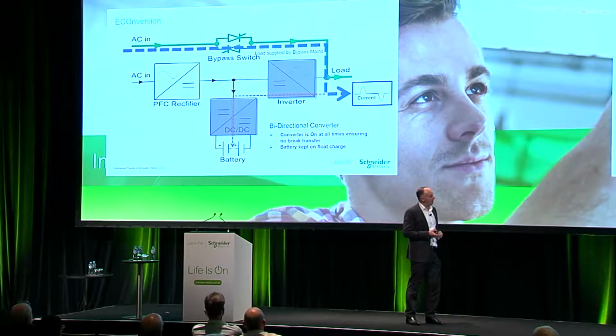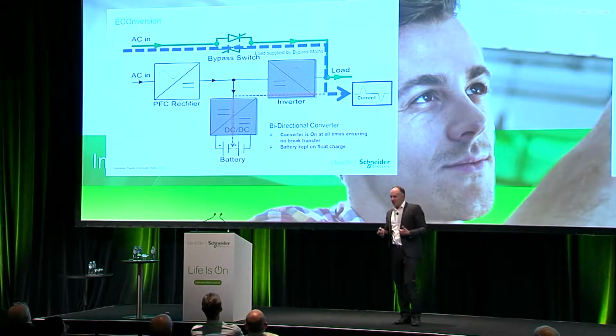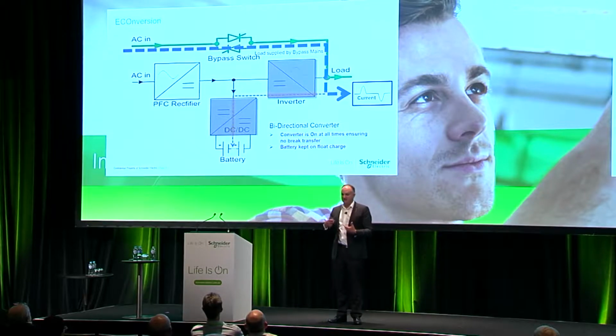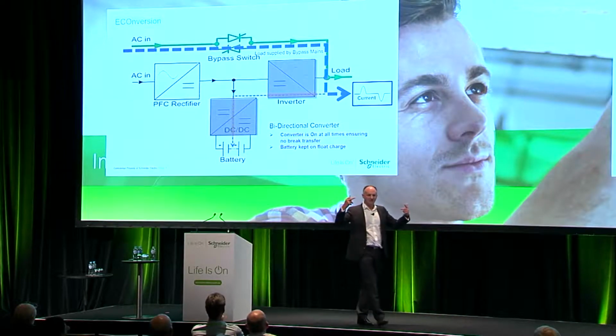So what e-conversion does is take the best of both worlds. If we look at our UPS architecture again, we do use that bypass input. In through the top, through that AC line, through the dotted line, comes our power and goes out to our load. And here's where it gets interesting. The way this works is like a big set of noise cancelling headphones. If you've been on a plane, you'll know how those work: they take in the noise and inject anti-phase noise to cancel it out. The same principle applies here. The inverter, which is now a bidirectional converter, injects anti-phase current into the load in order to cancel that out.